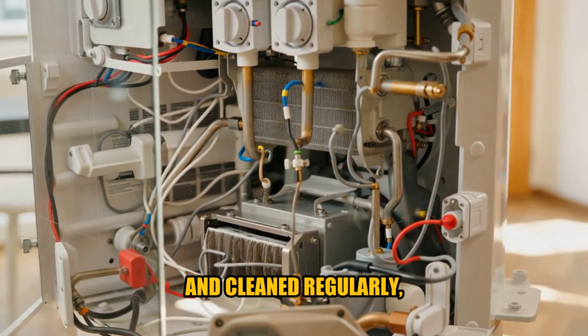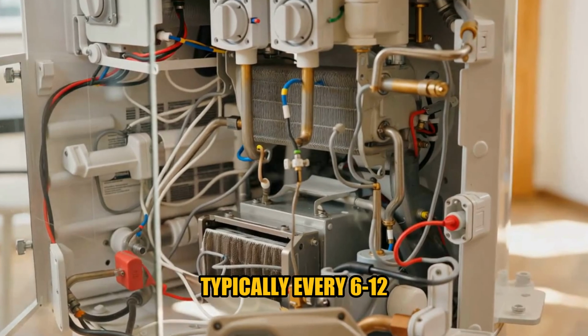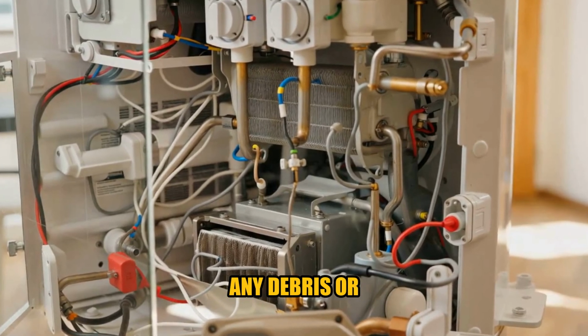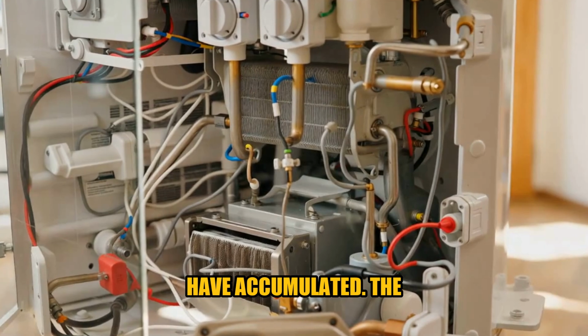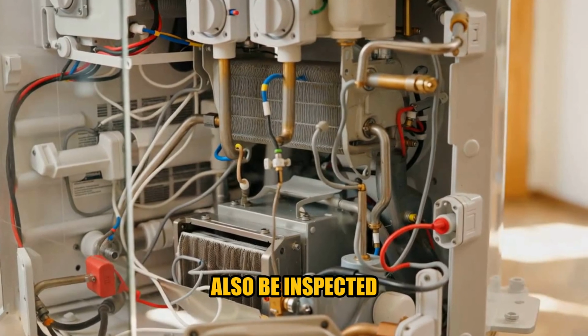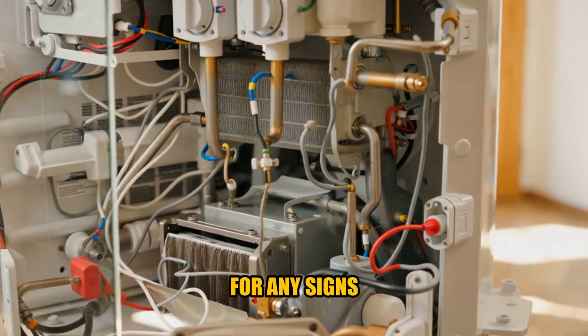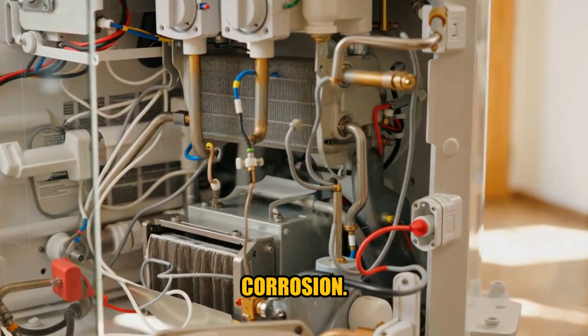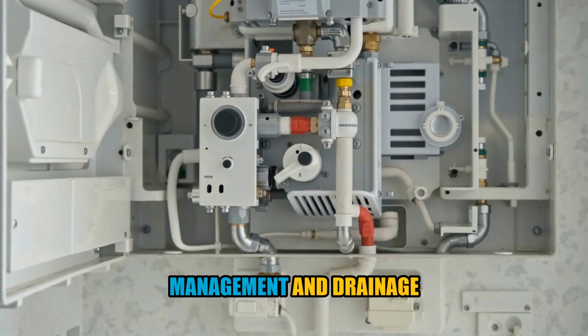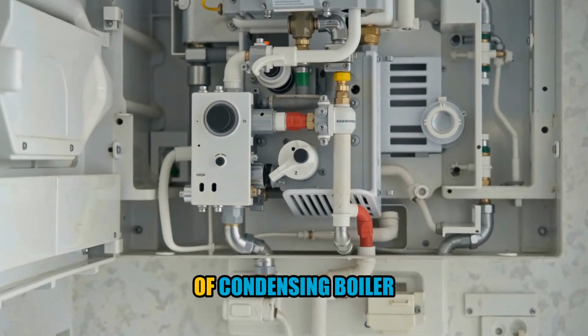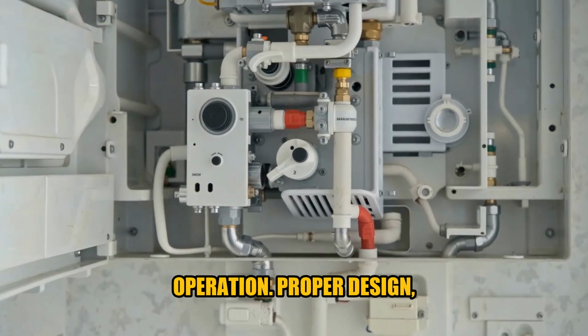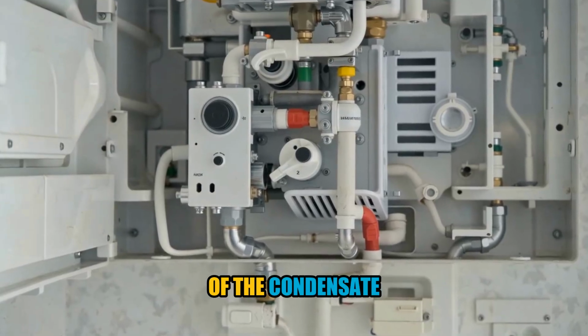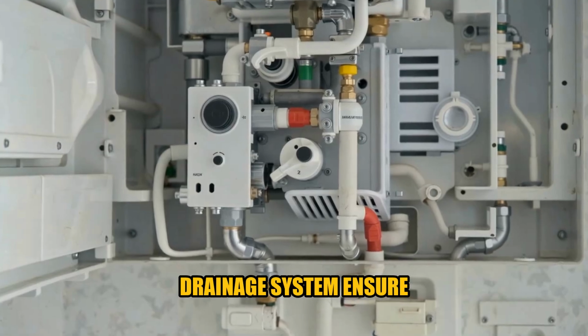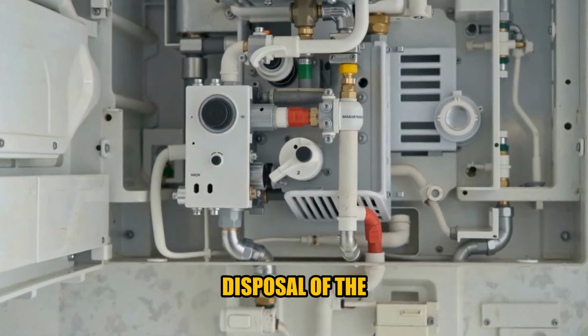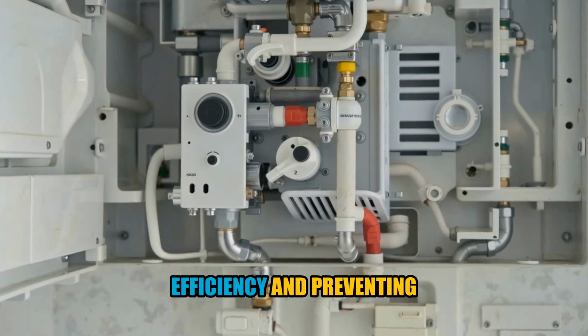The trap should be checked and cleaned regularly, typically every 6 to 12 months, to remove any debris or sediment that may have accumulated. The drainage pipe should also be inspected for any signs of damage or corrosion. In summary, condensate management and drainage are critical aspects of condensing boiler operation.